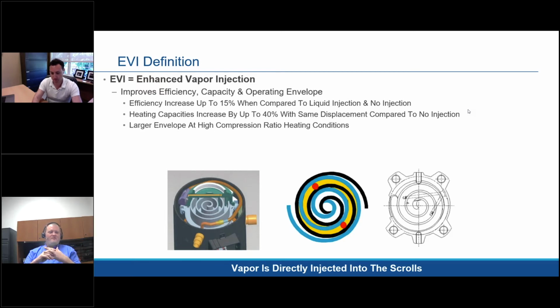So here's a little bit more detail on vapor injection. At the bottom left, you can see the top end of the compressor. We have a port right here on the compressor, just above the terminal box. That port is coming around, and it's dumping vapor into the scrolls to keep them cool. That will drastically increase your capacity because you're bringing in more vapor to compress that will push out into that condenser as well. And like I said, it increases your efficiency quite a bit, because it may be a 40% increase in capacity, but your power is only going up 25%, and you're going to get that 15% increase in efficiency due to that difference in power and capacity. This definitely increases the operating envelope that you would use for hot air or hot water conditions at low ambient conditions.